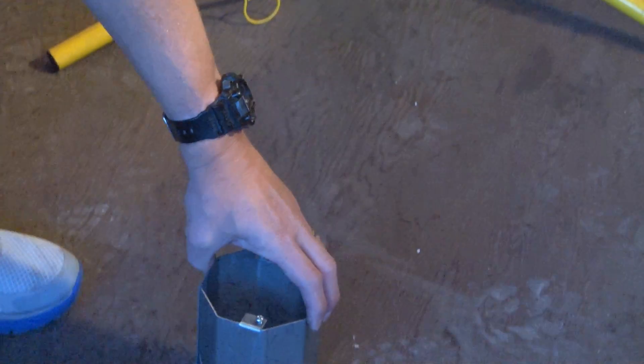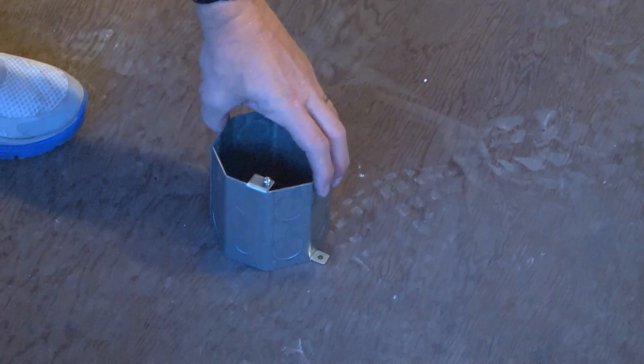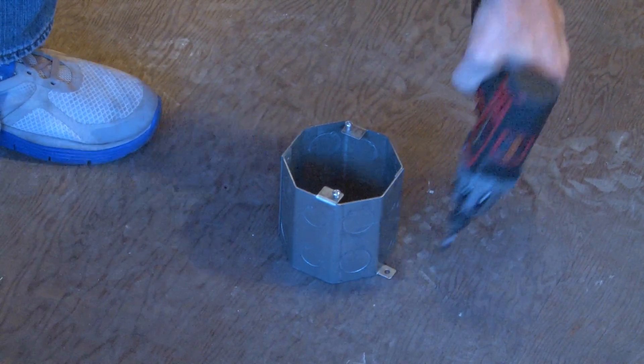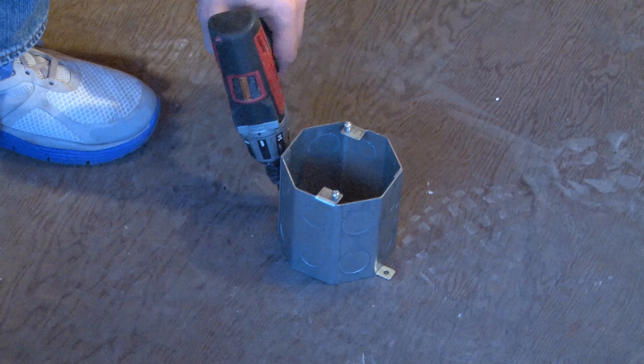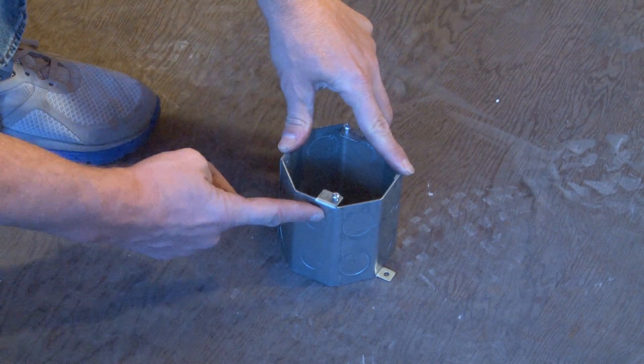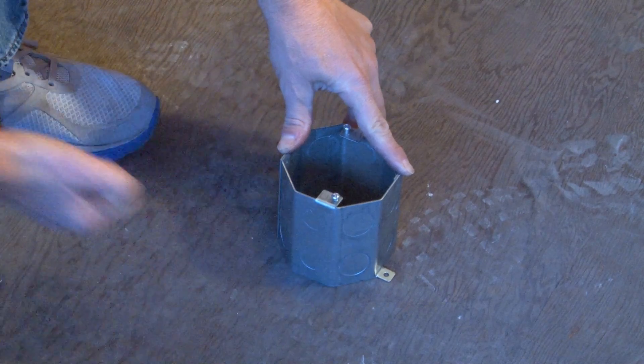The way it's installed is that the box is set directly on the form, and then a screw gun is used on the external feet to screw it directly to the wood form. Conduit knockouts can be removed and conduit installed.